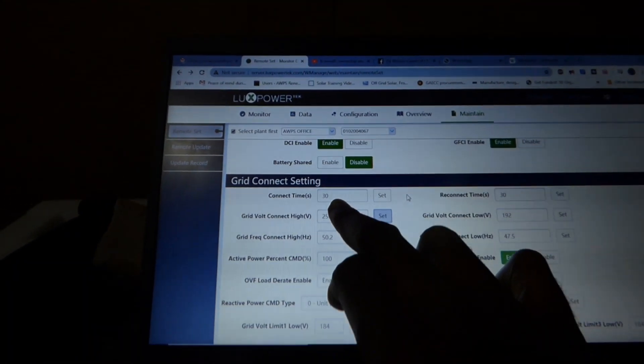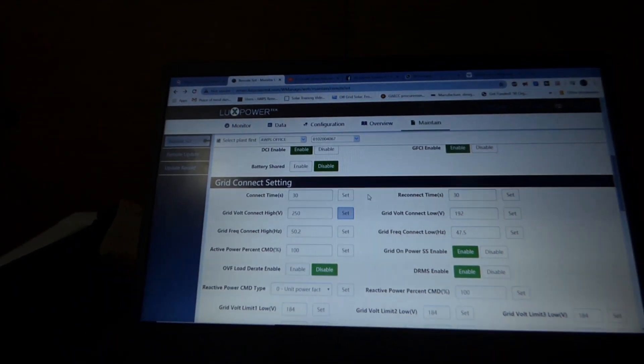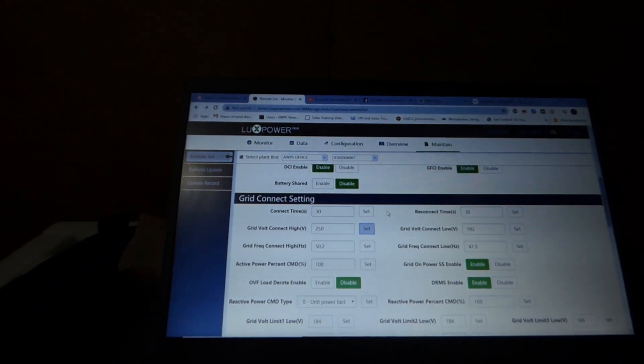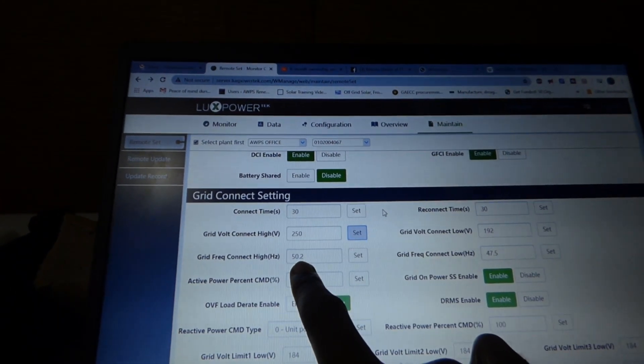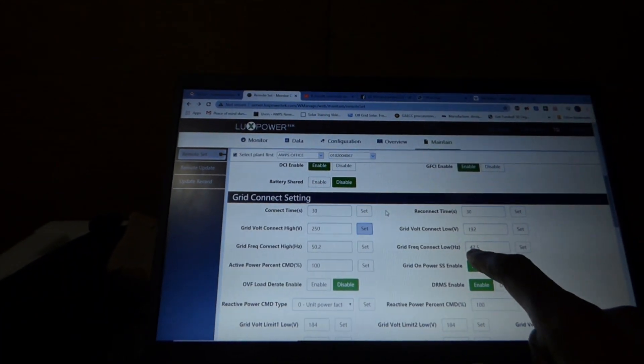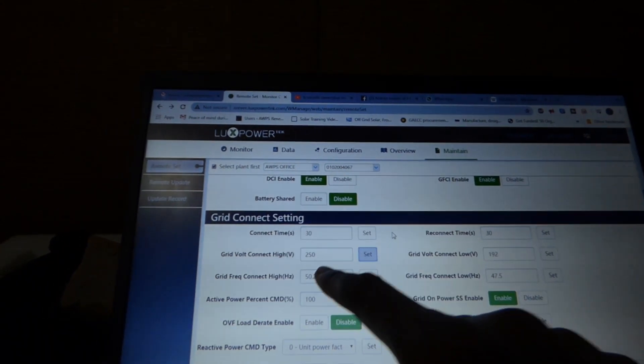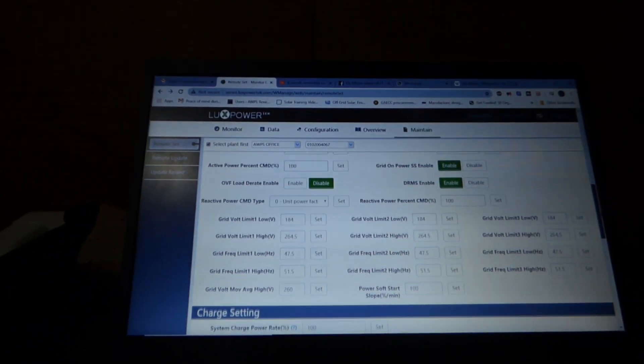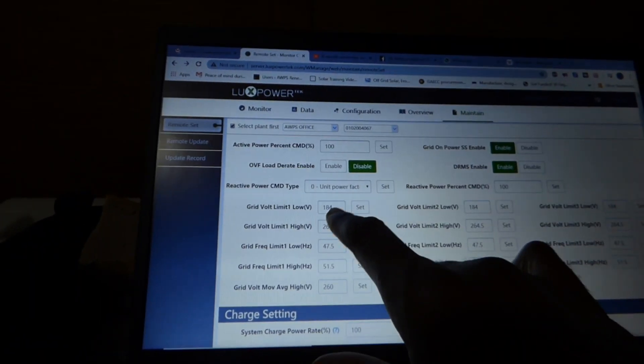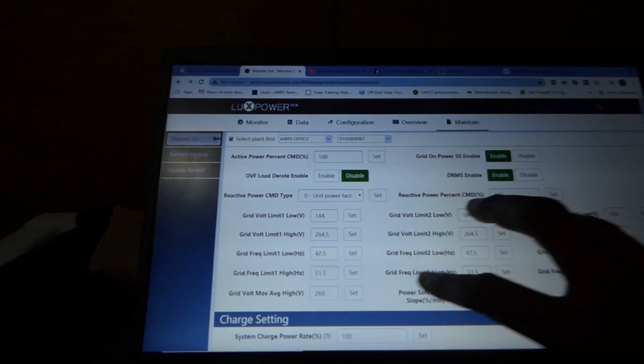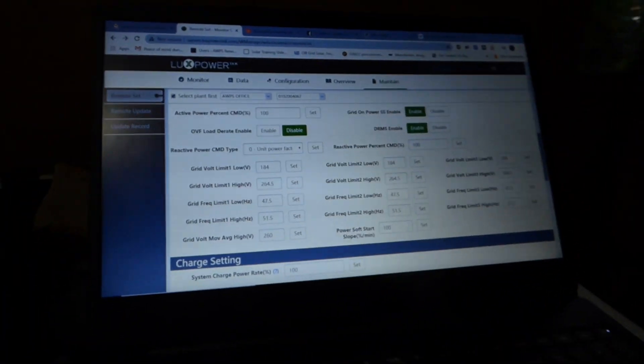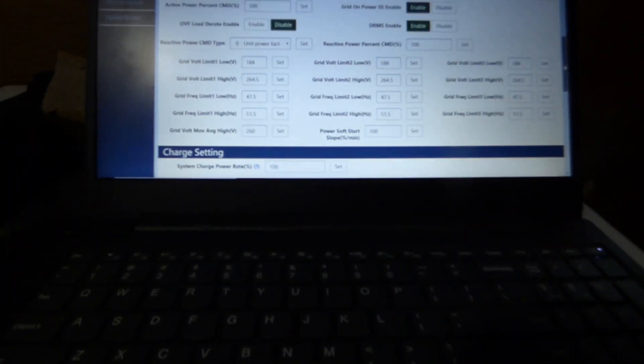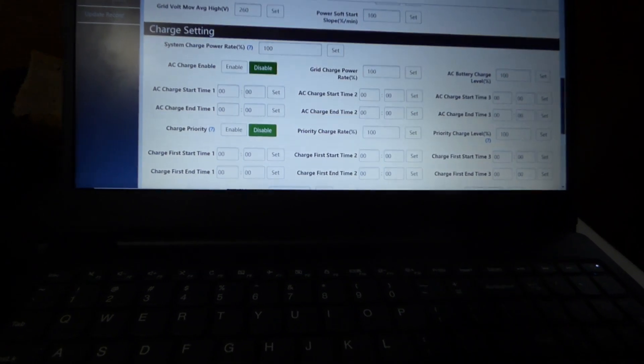Click okay. Connect time. I think that's 30 seconds. That's how long it should take to connect. Reconnect time 30 seconds. So it comes in. It takes 30 seconds before it hands over from the battery to the grid. Frequency. I can change this. I can make this 50 instead of 50.2. This is high connect frequency. Grid frequency, grid frequency low frequency. So between 47 and a half and 50.2 is what we set it to be. Read on power. So all these settings, I can change all the settings. For example, I can change the grid limit voltage, what the minimum is. I can say what the maximum is. I can say what the minimum frequency, all these things I can set here. Once I set it, it pushes it into the inverter. So I don't need to be pushing all these buttons here to change the settings. I do that on laptop in real time and it sends it right to the inverter.